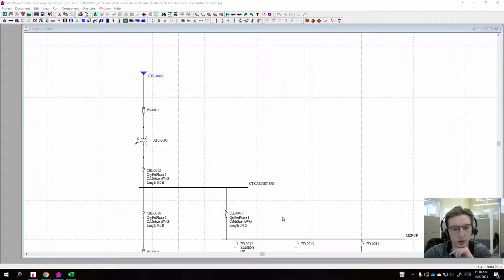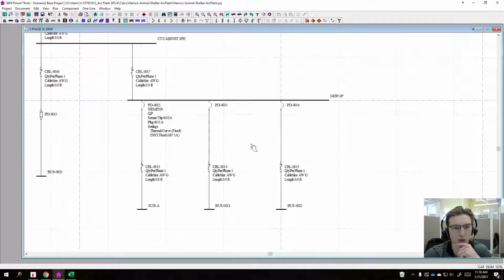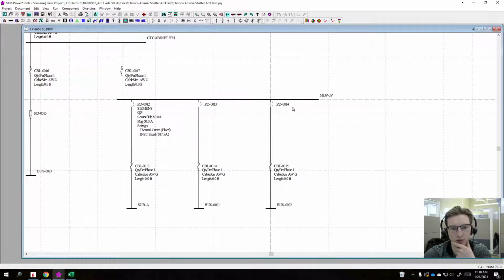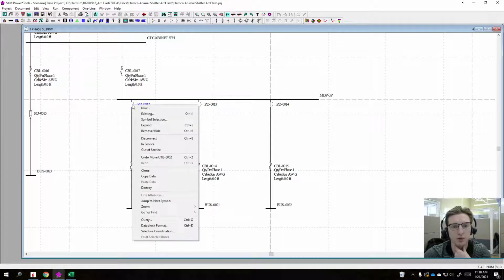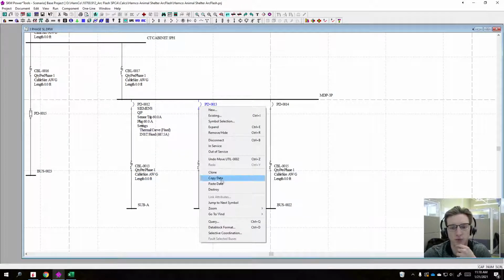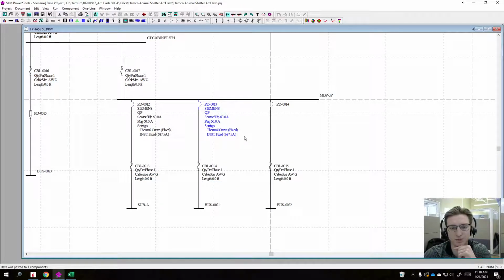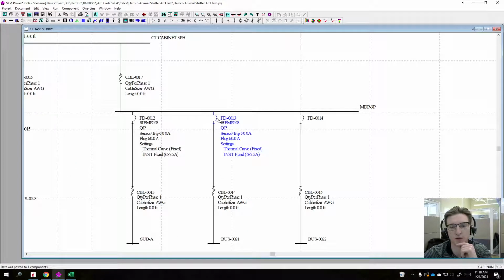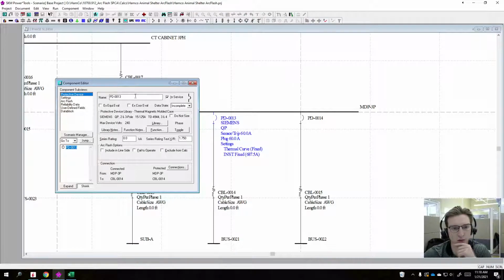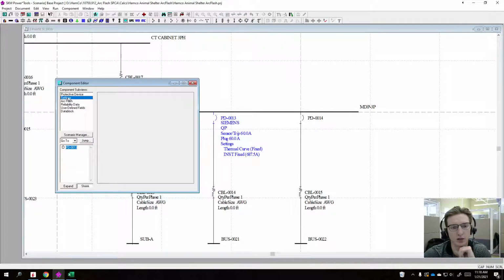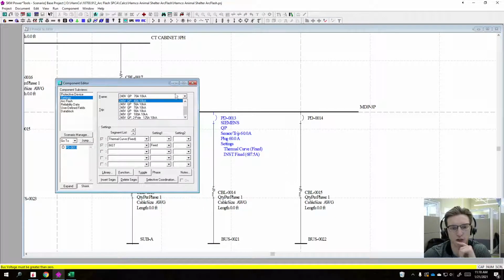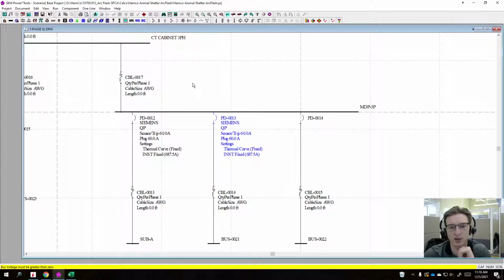Now we're going to talk about how you can quickly apply data across several instances. Let's say this breaker right here is a QP. I would just right click on it, go to copy data, then paste data, and that comes in. Notice the breaker names are still independent, which is what we want. If I need to change the trip settings, it's a double click, then go to settings and you can change it in here. That's a quick way to copy the type of breaker that you have.